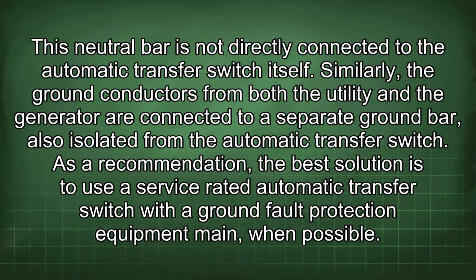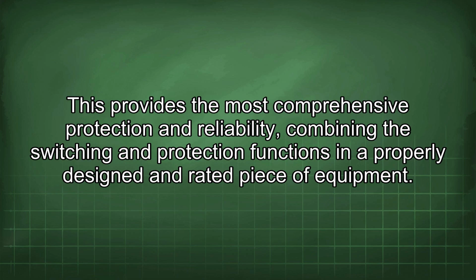As a recommendation, the best solution is to use a service-rated automatic transfer switch with a ground fault protection equipment main when possible. This provides the most comprehensive protection and reliability, combining the switching and protection functions in a properly designed and rated piece of equipment.